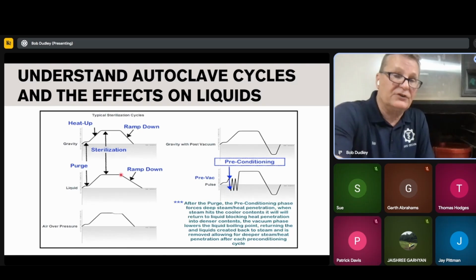You're running a liquid cycle. You don't understand it. You call your technician. Let me explain what happens. So after the sterilization time is completed, you've run a 45-minute sterilization. Everything shuts off. No steam goes into the jacket, chamber. Everything just sits still for approximately a minute to a minute and a half.